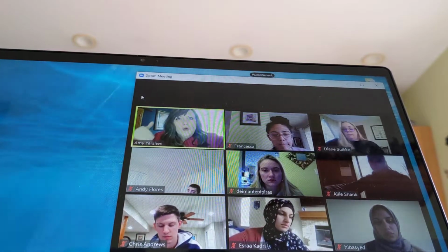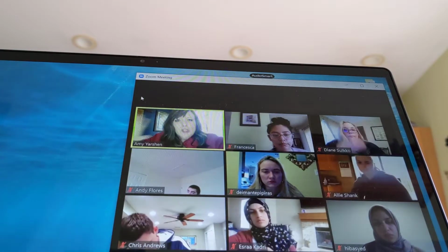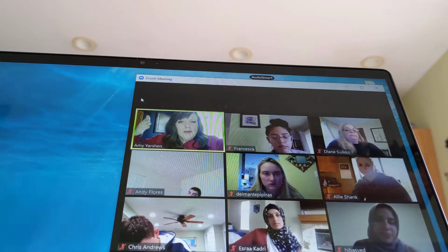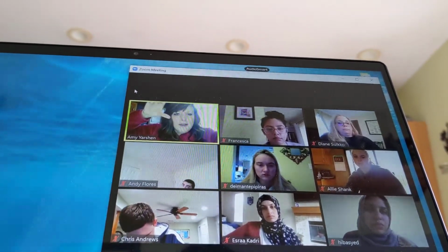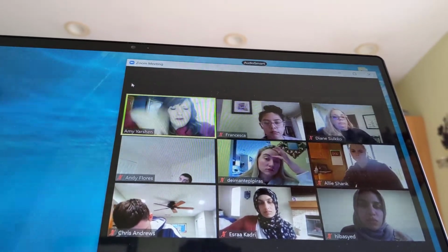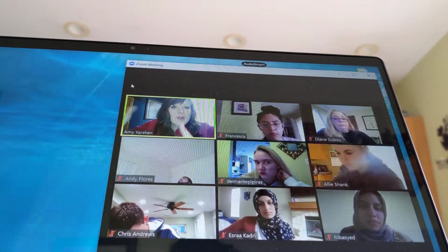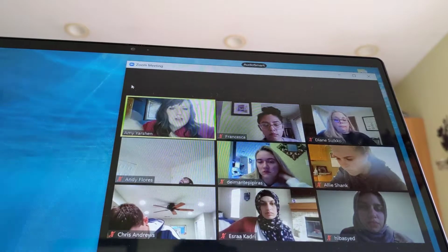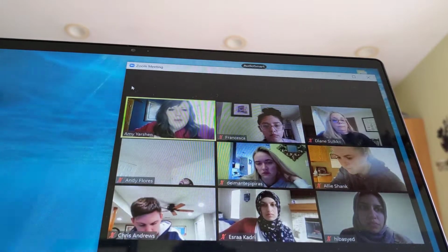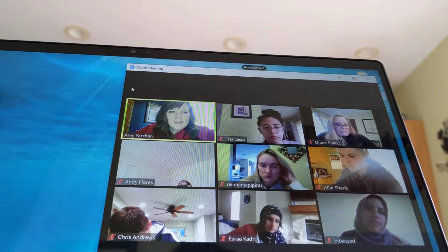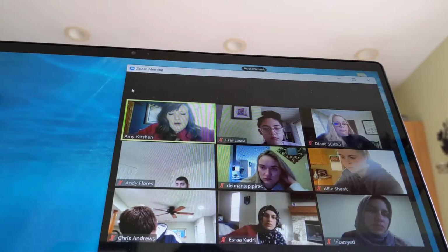You know, more general. When do you do them and how do you do them? Francesca showed us the glove that you hang the source in, right? So you make sure it's not contaminated. We hang the source, however we have to do it to flood the camera. We leave the collimators on or take them off. All general, not real specific on specific sites or anything.